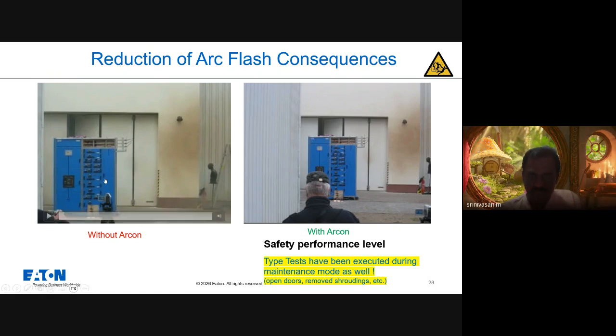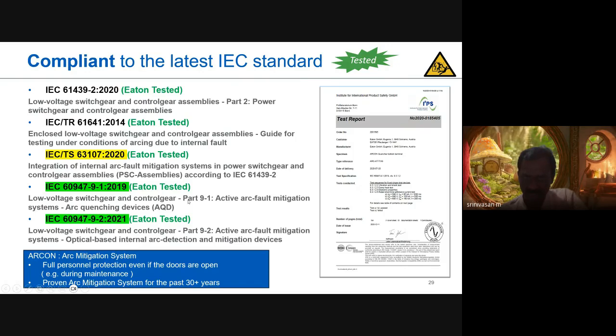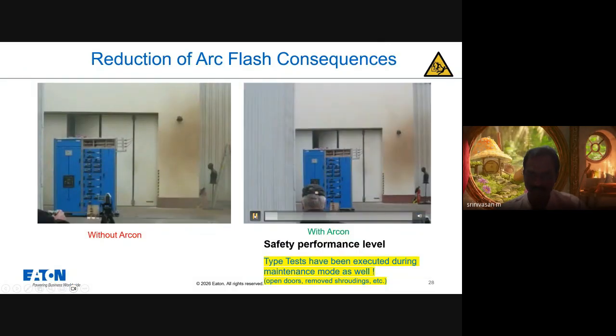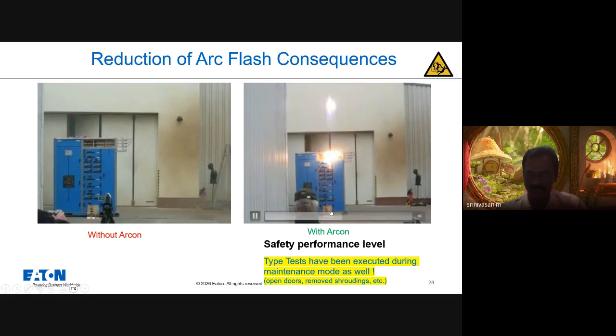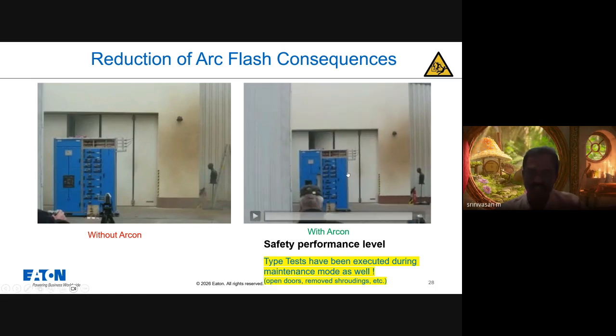In the same switchboard, after installing the Arcon, you could see the impact. You could see some small carbonized gas emitting from the board, which is very negligible compared to the case where the switchboard does not have the Arcon. Even when we did the test, the door was completely closed in the earlier case. But in this case, we kept the breaker compartment door open. So that means the level of safety to the human being, when the Arcon is installed inside the switchboard, is the very highest.